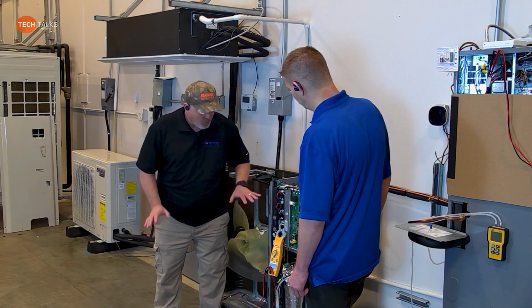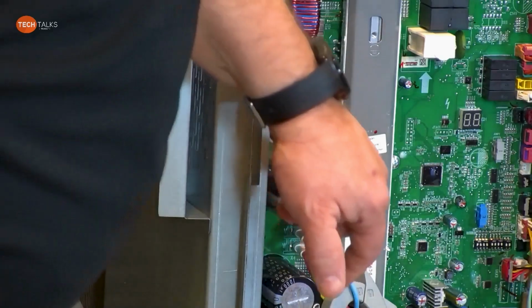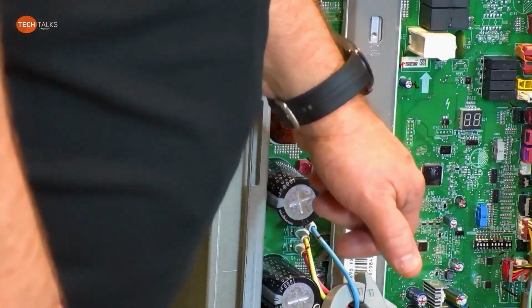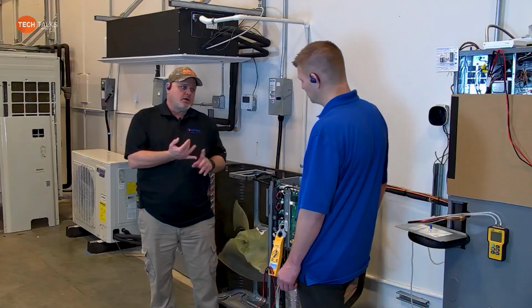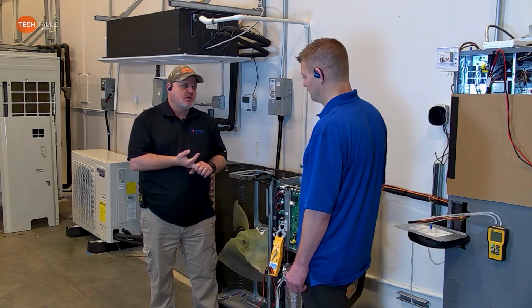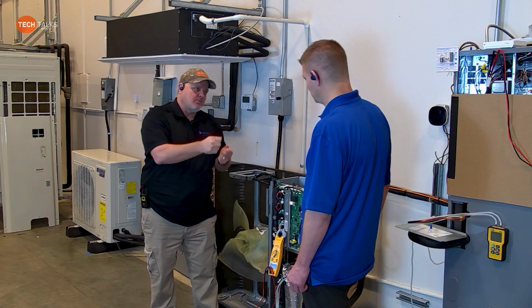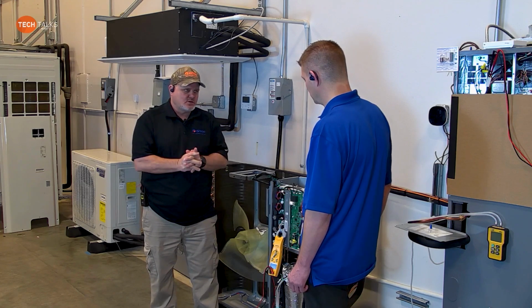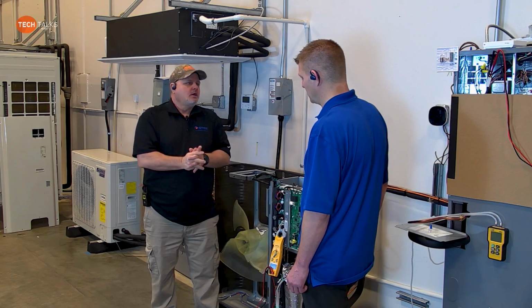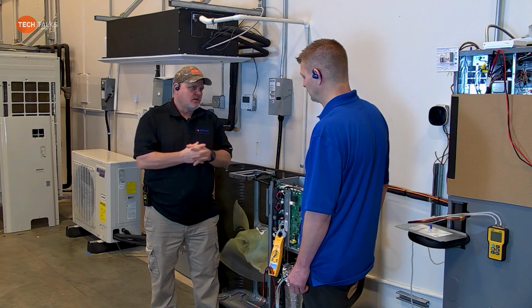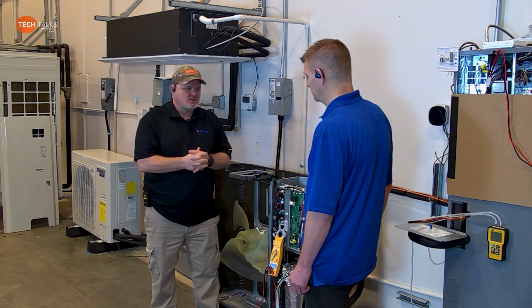So when you're working on the FLEXX units, when you have easy access to that DC bus like that, before you start unplugging and plugging anything, before you get your hands in there, get your meter leads in there, make sure that DC bus voltage has come way down. I would say if you get below 10 volts, chances are you're not going to hurt anything.